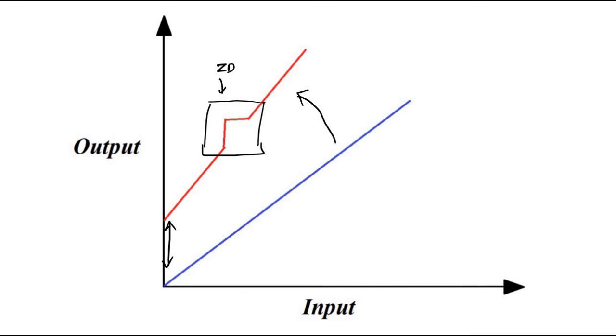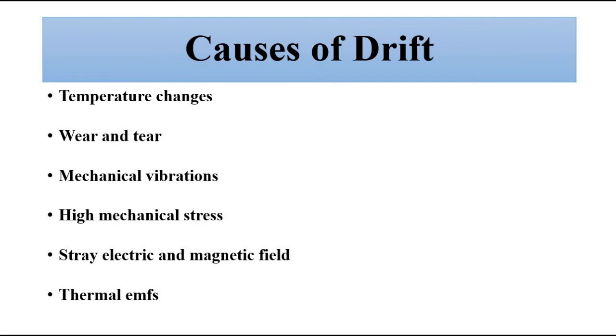The next question is: why does drift occur? What are the causes of drift in a measuring system? There are various reasons: changes in environmental conditions such as temperature and pressure, wear and tear from prolonged use, mechanical vibrations, high mechanical stress from long-term use, aging of components, stray electric and magnetic fields when electrical or electronic systems are used, and thermal EMFs.